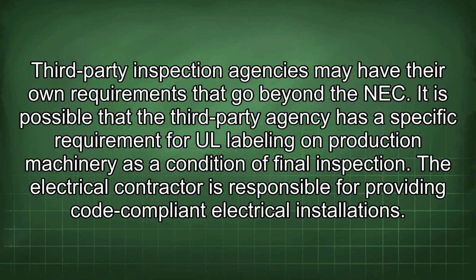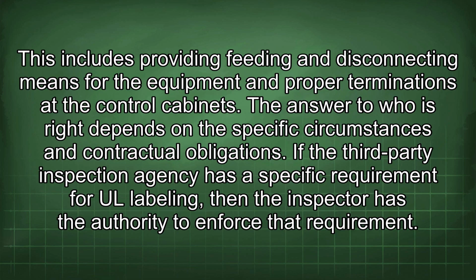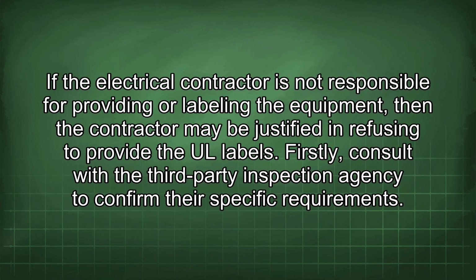of final inspection. The electrical contractor is responsible for providing code-compliant electrical installations. This includes providing feeding and disconnecting means for the equipment and proper terminations at the control cabinets. The answer to who is right depends on the specific circumstances and contractual obligations. If the third-party inspection agency has a specific requirement for UL labeling, then the inspector has the authority to enforce that requirement. If the electrical contractor is not responsible for providing or labeling the equipment, then the contractor may be justified in refusing to provide the UL labels.